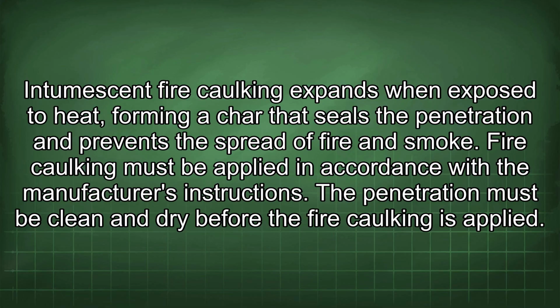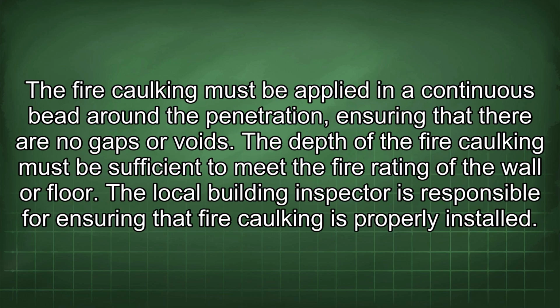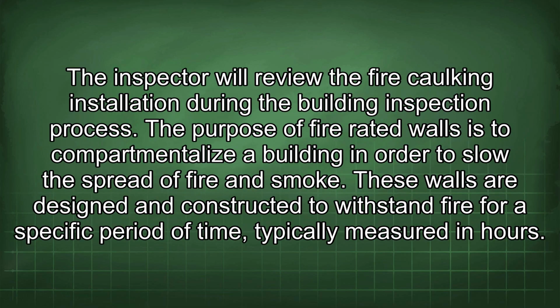Fire caulking must be applied in accordance with the manufacturer's instructions. The penetration must be clean and dry before the fire caulking is applied. The fire caulking must be applied in a continuous bead around the penetration, ensuring that there are no gaps or voids. The depth of the fire caulking must be sufficient to meet the fire rating of the wall or floor. The local building inspector is responsible for ensuring that fire caulking is properly installed. The inspector will review the fire caulking installation during the building inspection process.